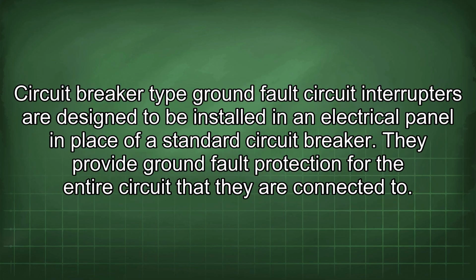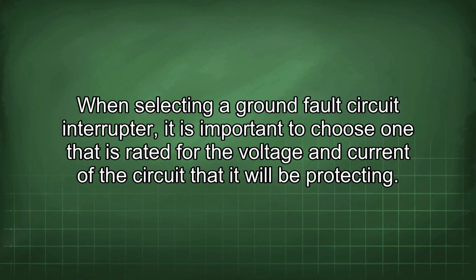Circuit breaker type ground fault circuit interrupters are designed to be installed in an electrical panel in place of a standard circuit breaker. They provide ground fault protection for the entire circuit that they are connected to. When selecting a ground fault circuit interrupter, it is important to choose one that is rated for the voltage and current of the circuit that it will be protecting.